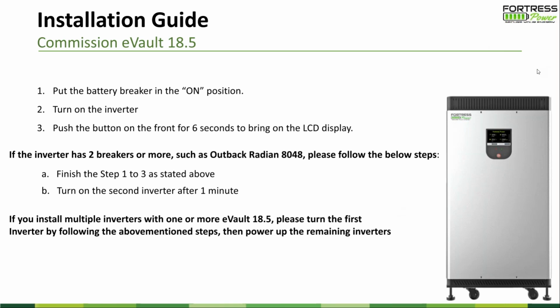So the same processes. A lot of inverter companies put multiple small inverters in one enclosure, so they make one inverter. So we just need to use the pre-charge circuit for the first inverter. When we start the second inverter, we don't need the pre-charge circuit because the surge power is relatively low. The system is able to handle it. So just follow the same process as the first step, and then turn on the second circuit breaker after 30 seconds or minutes, so that the LED system starts smoothly.